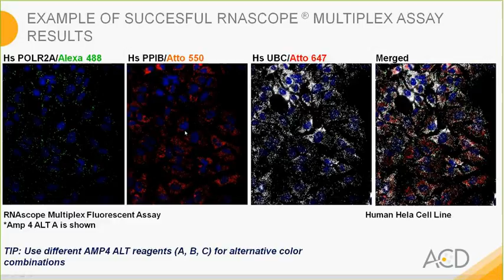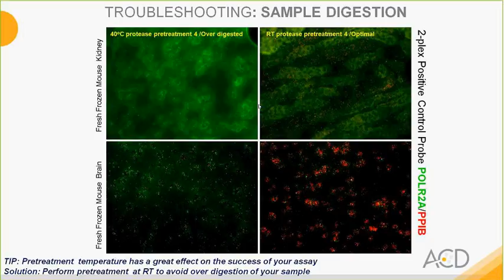Now, let me talk about some troubleshooting tips for the multiplex assay. A very commonly observed issue that we have come across is sample overdigestion. Again, the example that I'm showing here is for a fresh frozen sample, and the recommendation is a protease digestion at room temperature. Sometimes if this particular step is done at 40 degrees, the sample gets overdigested, and here is what I'm showing as an example of an overdigested sample. The best way to fix it is running the protease digestion at room temperature.